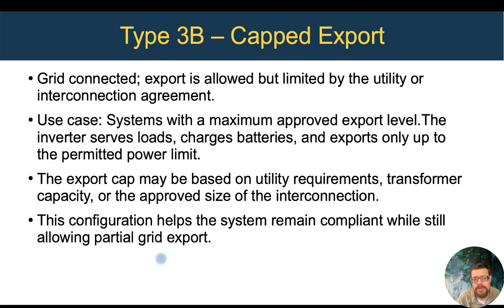Sometimes it's an issue that you're backfeeding a 200 amp panel, you can't backfeed it with more than 32 amps. So you need to limit that backfeed to 7,600 watts. So a Type 3B system, we can export some, and we can set a limit on that export to maintain compliance with limited transformer sizes, limited feeder sizes, or limited amperage of our interconnection point.